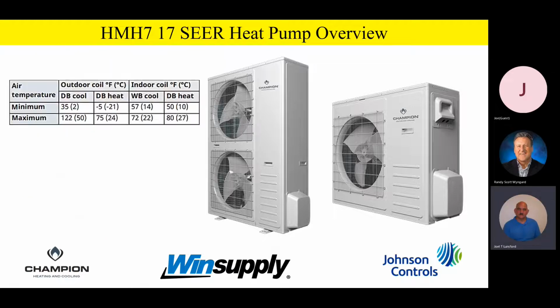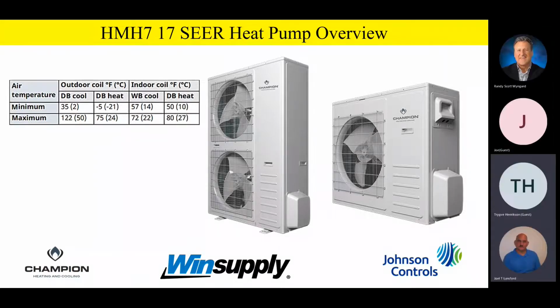Another thing that we get questions about is, what is the unit capable of as far as minimum and maximum temperatures concerning outdoor as well as indoor air temperature. So this is right out of the install information. This can be found if you go to your Navigator website. You'll be able to pull down the install information and actually see this. But as you can see, the minimum cooling on the outdoor is going to be 35 degrees. And minimum heating is going to be -5 degrees right out of the box. Indoor coil 57 wet bulb for cooling and 50 degree on the heat for heating.